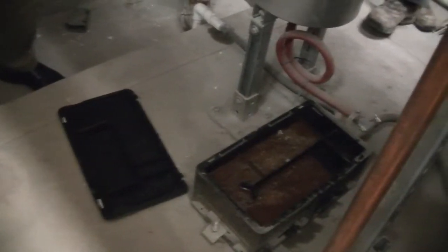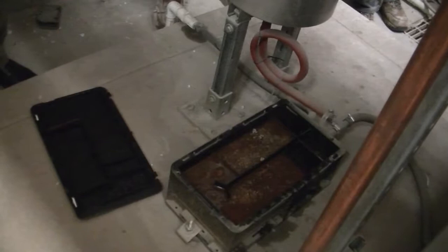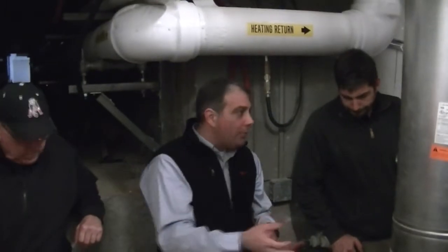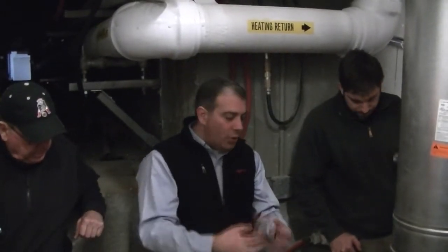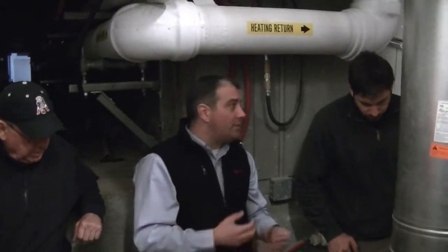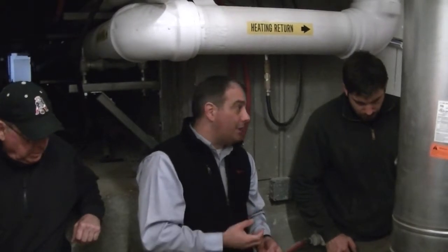Now, the one thing that you want to be careful of is what you see here. Over time, depending on what we're sucking in for combustion air and things like that, you'll start to get dirt and sludge collecting on those lime pellets. It's not going to hurt the operation of the boiler. The problem is if there's a coating on those lime pellets, it prevents them from neutralizing the condensate.